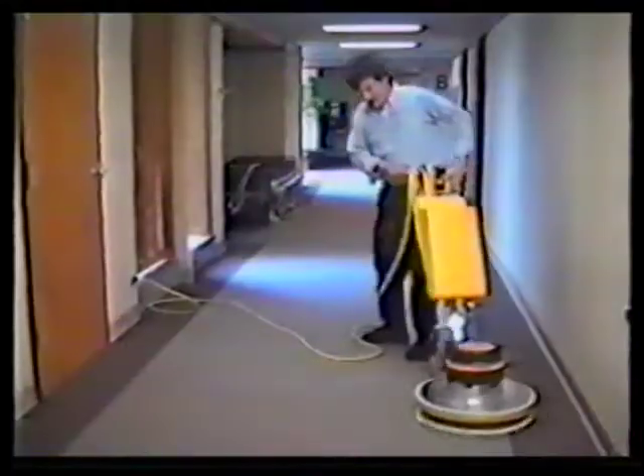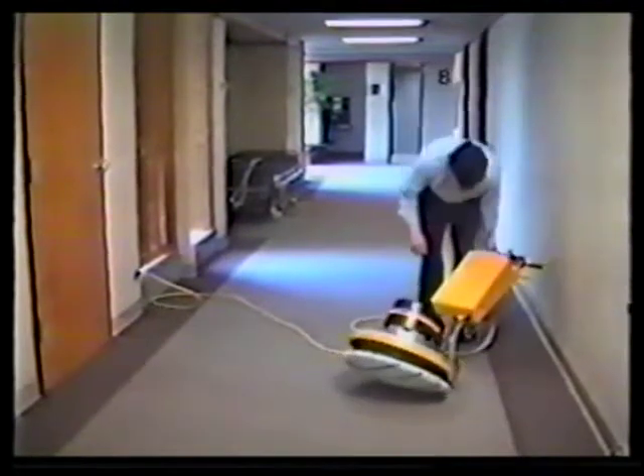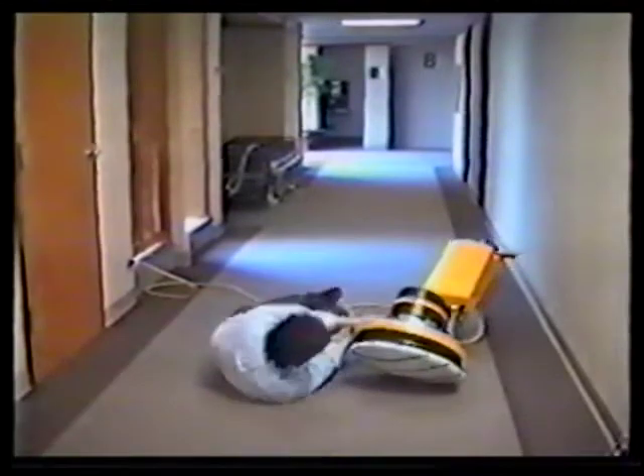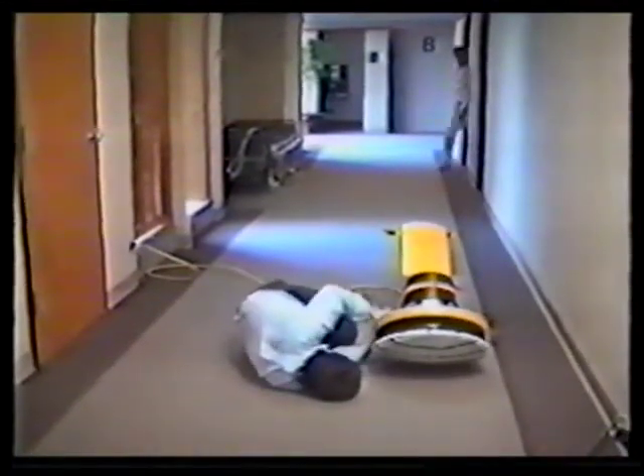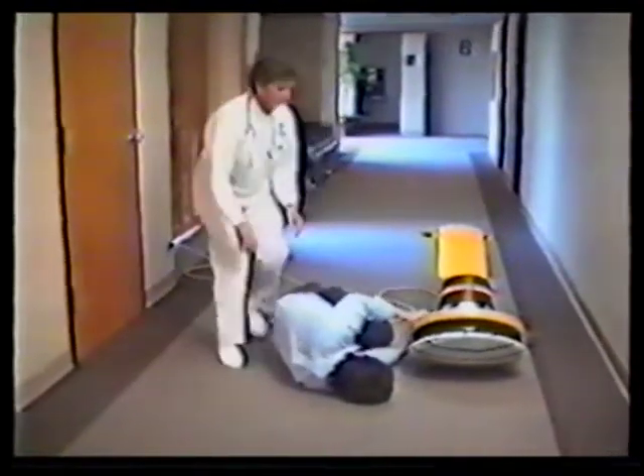One thing that can happen if there's a prolonged exposure to direct current is that the muscles become tetanic and the patient will grip the current source and be unable to let go, and this could further potentiate the injury. So these are examples of macro shocks, macro shock being an electrical exposure of sufficient intensity to be perceived by the patient as some form of a shock.